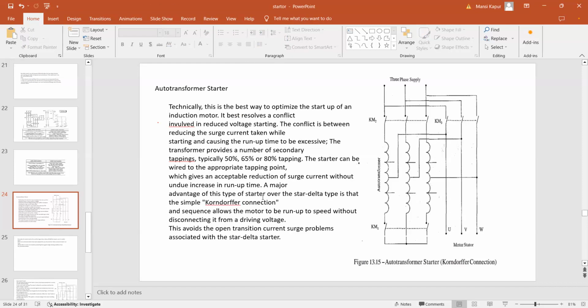A major advantage of this type of starter over the star delta type is that a simple connection and sequence allow the motor to run up to speed without disconnecting. So in the star delta there was a disconnection time when it is switching from star to delta, but here there is no disconnection time. Yes, this avoids the opening transition surge problem.